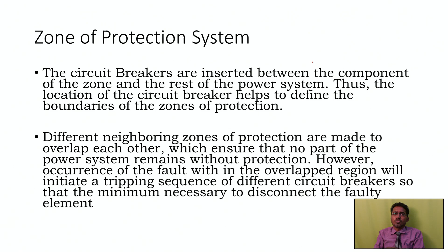For a single area, 1 or 2 circuit breakers will act as protecting zones. That is the overlapping of protection. Zone protection is nothing but a single circuit breaker present in 2 zones. Overlapping of zone is nothing but the protective area being covered by 2 different circuit breakers in different zones. That point is considered as overlapping of protection. That's the point I have given here. Overlapping zone has a powerful advantage.